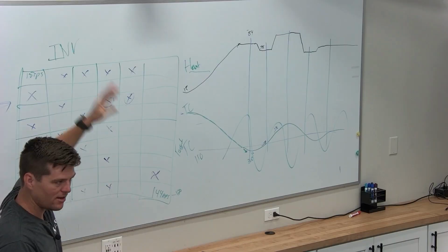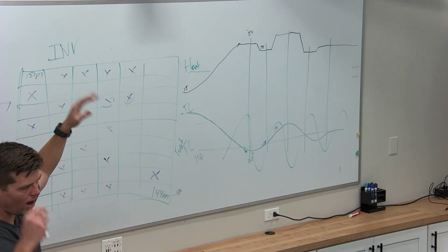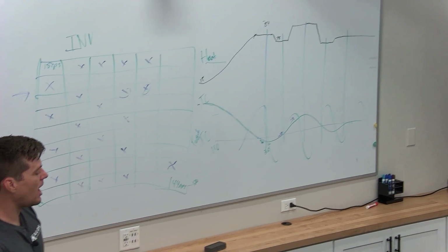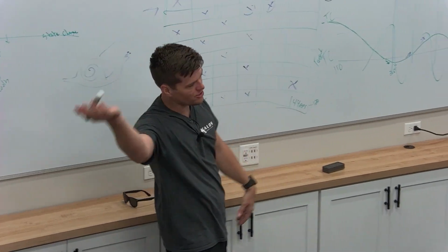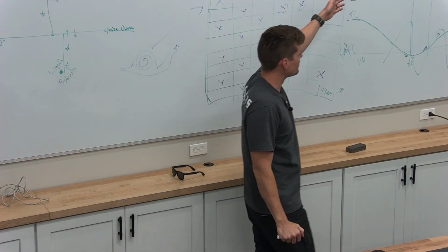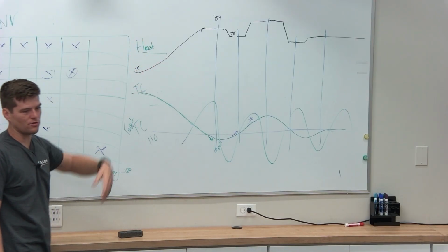And if I look at my targets and it's erratic, then I say, okay, what's up with that? Why am I open, close, open, close, open, close? And you might find that it's going into high pressure step down and then high discharge temperature step down and then coming out and then going in and then coming out. What controls compressor speeds erratically is also safety controls.